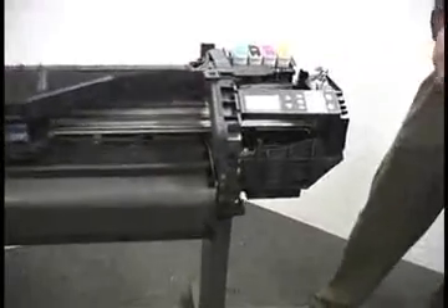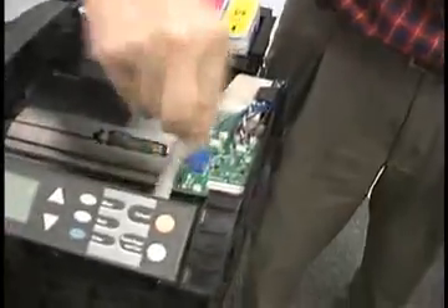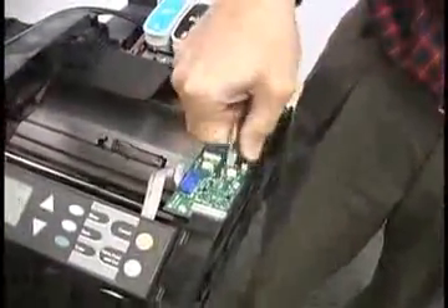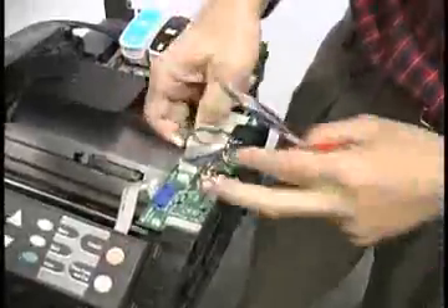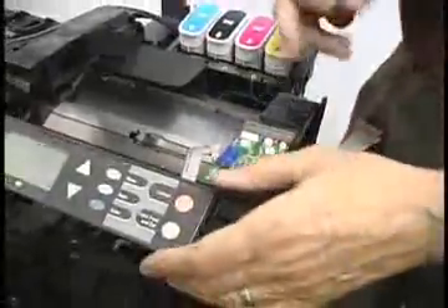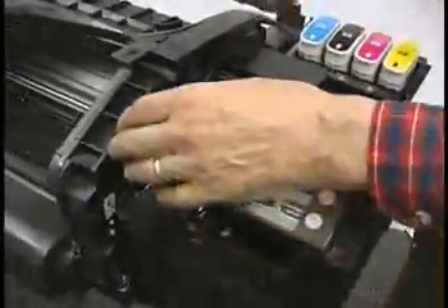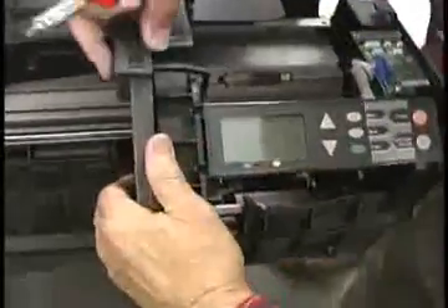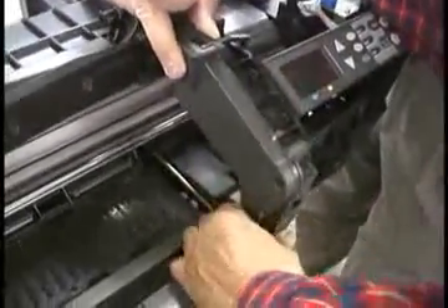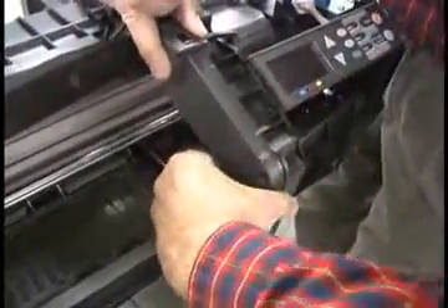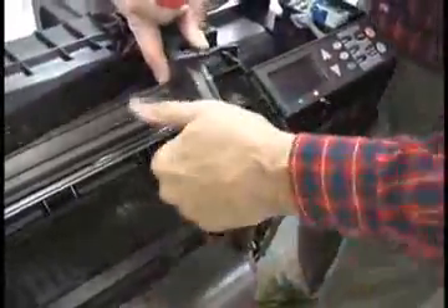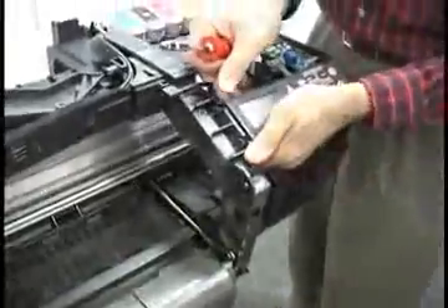Okay, we need to disassemble just about everything that's on this side of the machine. So we start out by unplugging all of the connectors on the interconnect board here. Move them out of the way. This board can stay on this assembly, but the display itself has to come off. Now this needs to get out of the way. There's a locating pin down inside here. If you pull that out, this will lift out. Now this just pops off like that. We can set these aside.